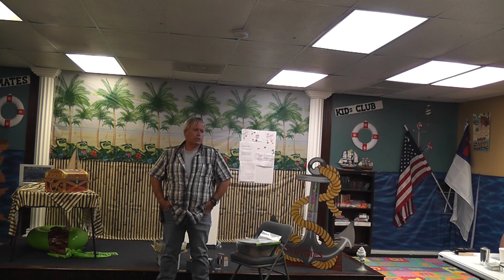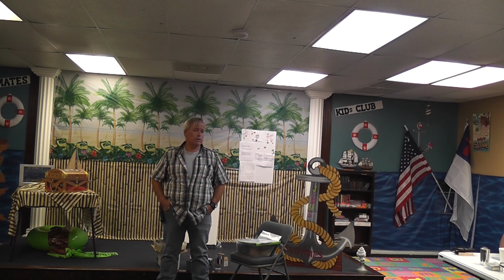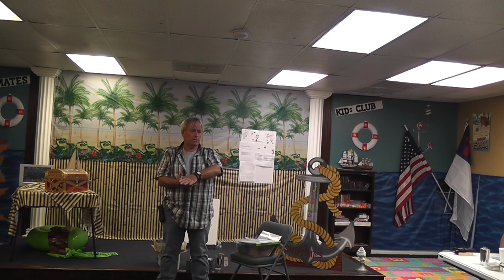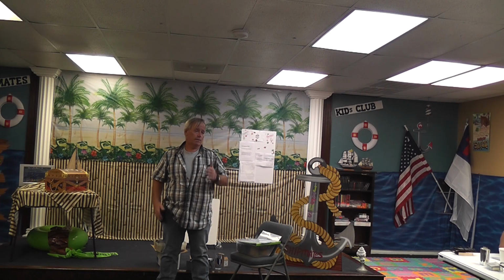When you open up machines on the ground, or 7 stories up, contactors work by an electromagnet. You're putting power to a coil to make an electromagnet to pull in the contactors. Ants are attracted to magnetic fields. They do go rooftop, and they will fill a contactor full of dead bodies and take a machine offline. Scrape it with the file. Yup. No, take your phone out and take a picture of it before you touch it. Yeah, this thing is riddled with corpses.